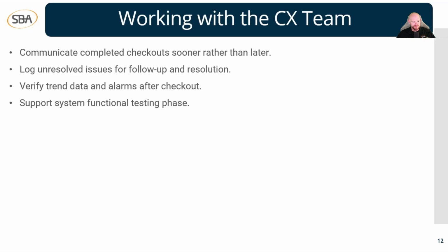And then the last point for this slide here is to support system functional testing phase. So we're supposed to support in the functional testing of our system because we've done the point-to-point checkout. We've verified that all this stuff works. So once we get into the functional testing, we can go back and look at this. If there's a problem, we can say, okay, well, it was working then. So what has happened? What has changed in between there? And then we can go back and look and see maybe if there was something in the software the commissioning agent changed. That could be why it's not working now. So again, documentation's huge for all this stuff, guys. Okay, that's what I keep trying to reiterate here. If you've got this documentation, it makes your job 10 times easier in the end.